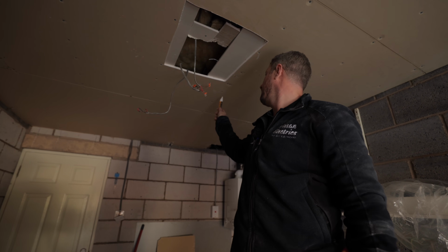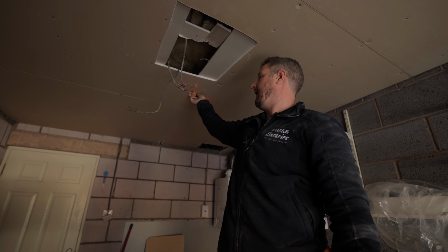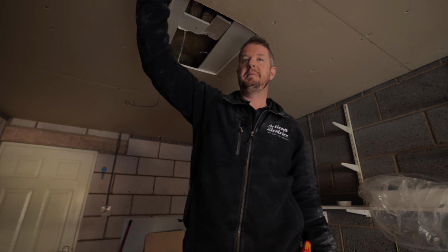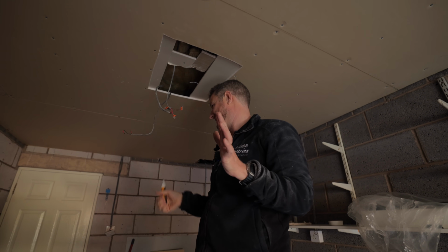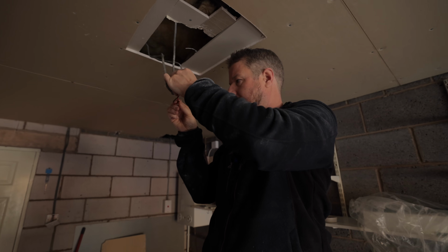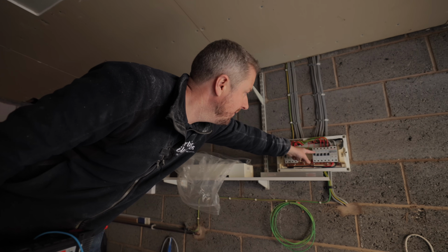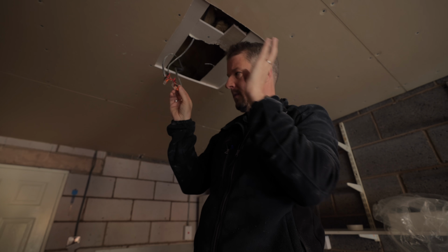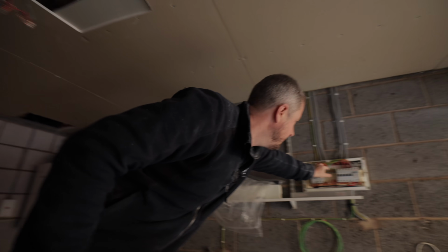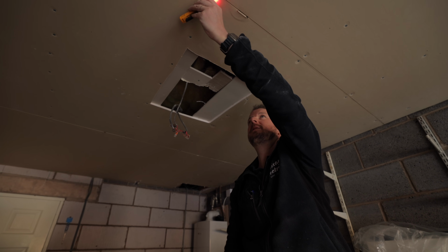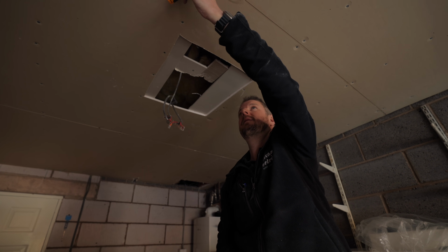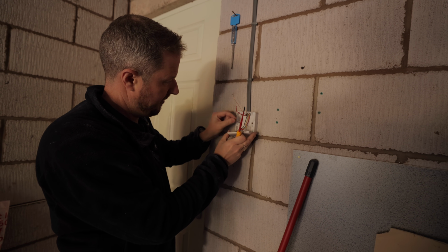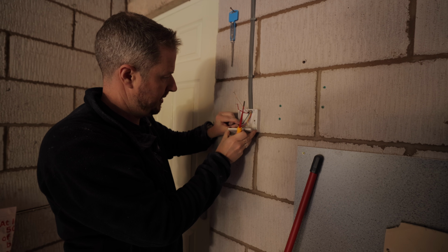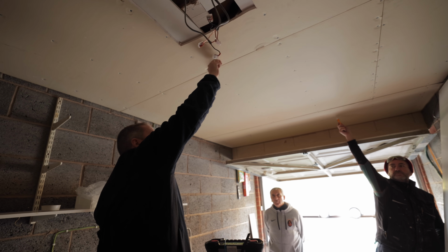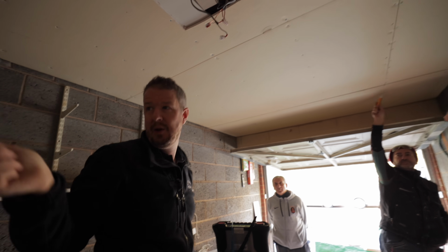We've got power here. Our ceiling is dead. Okay, so we're making progress. Now let's connect this one and see if any problems come back. Okay, so now our switch is connected. Ceiling's live again. So it's got to be something to do with this switch. So that is the permanent live coming down to the switch and the switch live. Disconnect those, turn it back on. No, right. So it's something to do with that two-way switch cable.